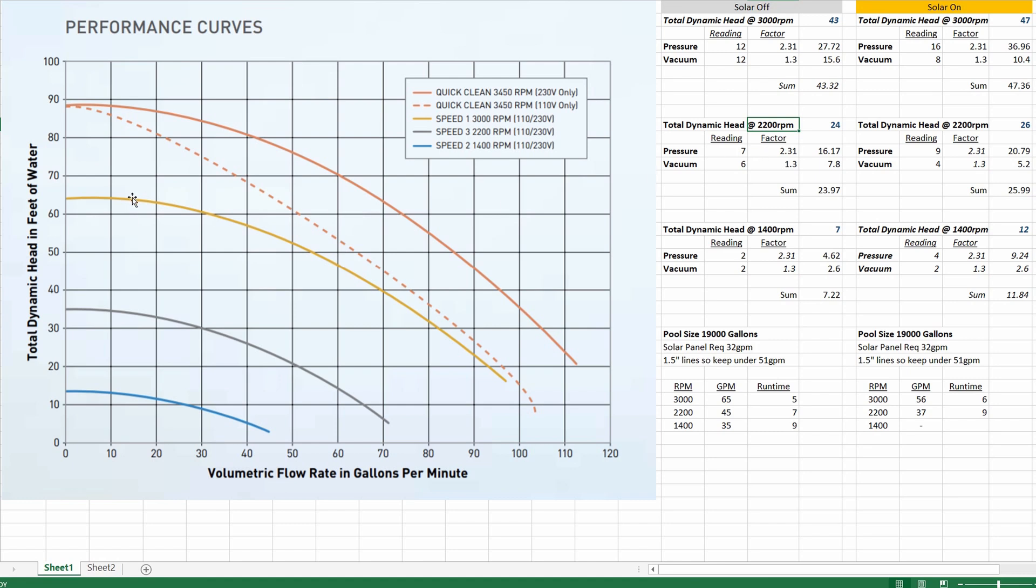And your total dynamic head is going to drop at a lower RPM so you need to use a different curve. So at 2200 RPM my pressure and vacuum readings were 7 and 6 respectively so again we use the same factor to multiply those values so now I have 16.17 and 7.8 and if you add those together we have just about 24 if you round up.